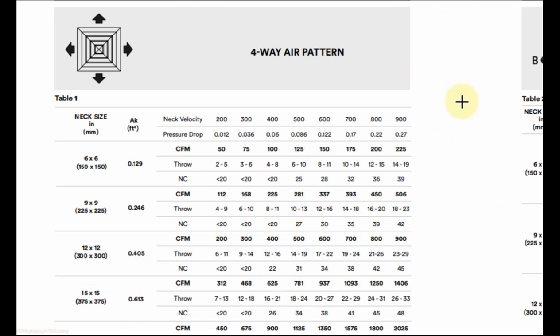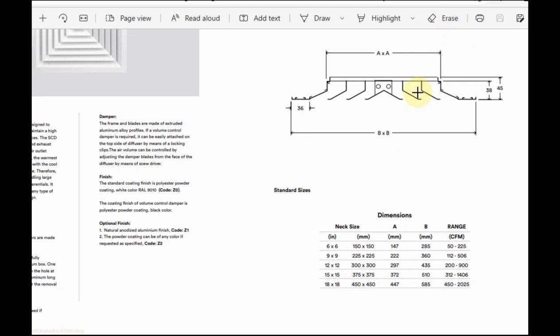So in this way you can select the square ceiling diffuser for any CFM. You need to calculate the throw and consider the NC level as per your requirement and also the neck velocity. It is the section of a square ceiling diffuser.